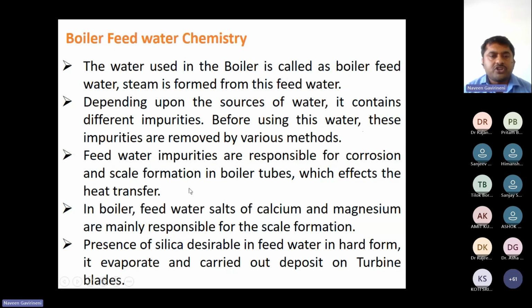Before using it, impurities should be removed, and feed water impurities are responsible for corrosion and scale formation in the tubes, as I explained. This also affects the heat transfer. Suppose we are using 90 tons per hour to get 150 megawatt of heat. If any scale formation happens, what happens? We are supposed to give excess coal to get that much heat.